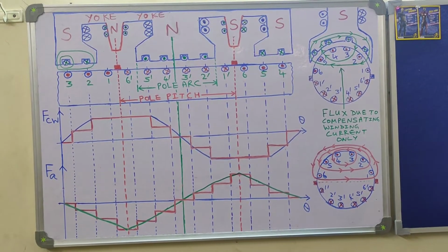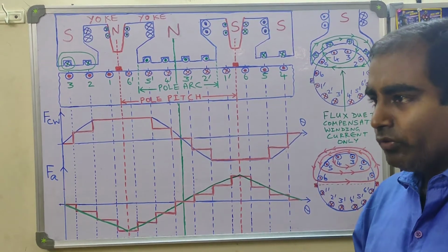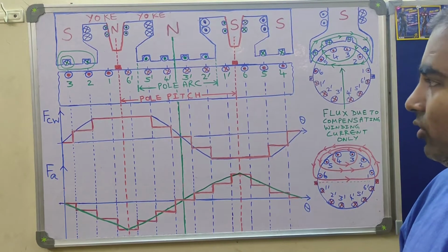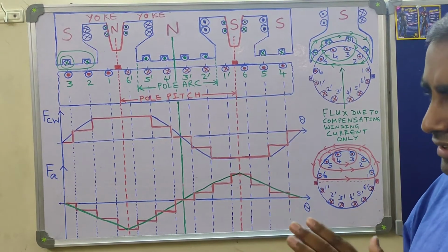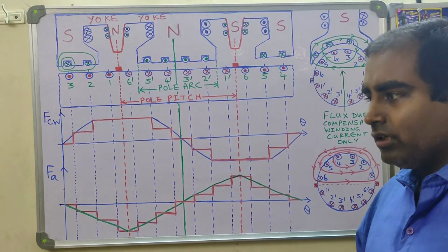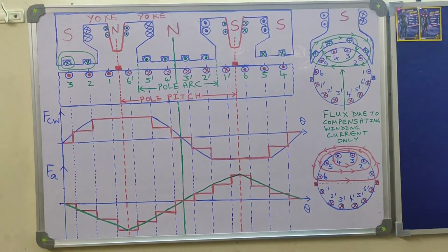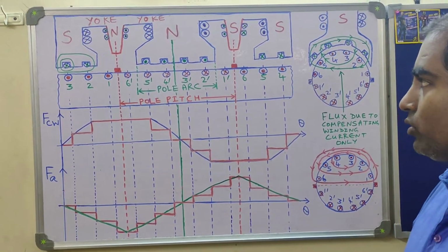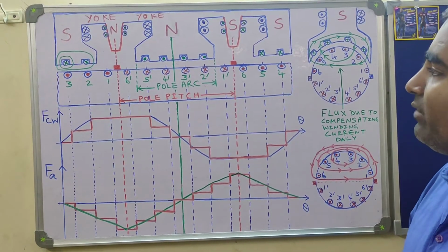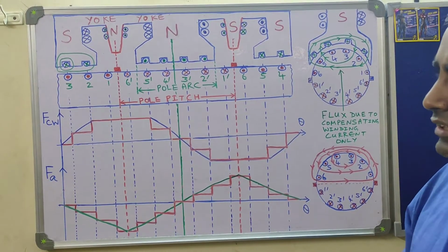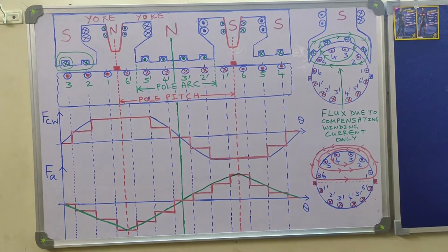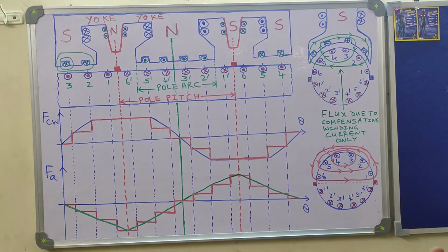The moment a lump of steel comes in between two rotating rollers, it requires a very high torque in order to compress the lump of steel and flatten it. So at that time the torque requirement goes up to a very high value. Now in case of a DC motor, if the torque requirement goes up to a very high value, then that can be met by drawing very large armature current. But again, very large armature current implies very strong armature reaction effects.